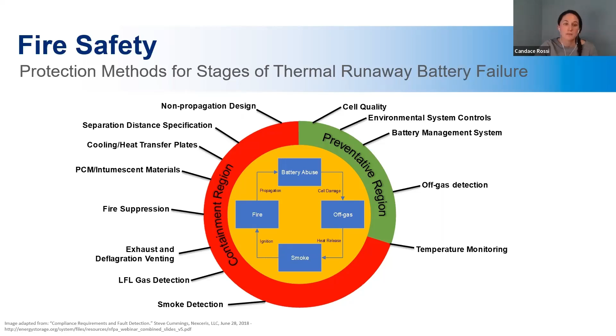And then as you're monitoring the temperature, there might become a stage where it's too late to prevent thermal runaway from occurring, so you'll have to work on containing it. This is where smoke detection becomes extremely important, as well as gas detection, exhaust and deflagration venting for these systems, different fire suppression methods, and cooling and heat transfer plates. There are specific separation distances that are required, and having a non-propagation design. These are all methodologies included in the code to help prevent or contain an event if one would occur. We'll go through the majority of those, and you'll see the different systems set up for storage to help prevent a fire.